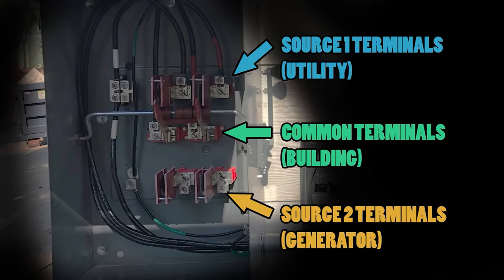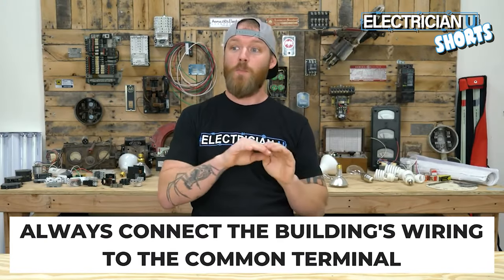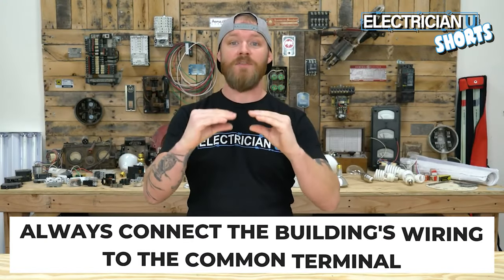Now in both cases — manual and automatic transfer switches — you're going to have terminals. You're going to have common terminals in the middle. When a switch is thrown in one position, a connection is made between this common terminal and one source, or the common terminal and another source. So you're always going to be hooking the building's wiring to that common terminal, because that's the one thing that never needs to change — the building's wiring is always going to stay the same regardless of what source of power you're coming from.